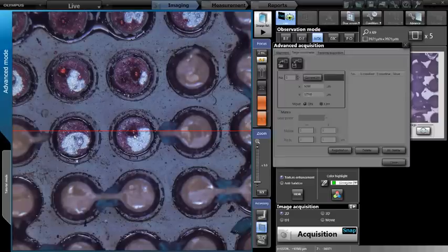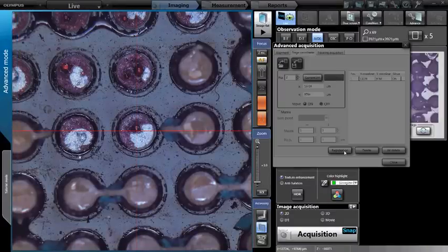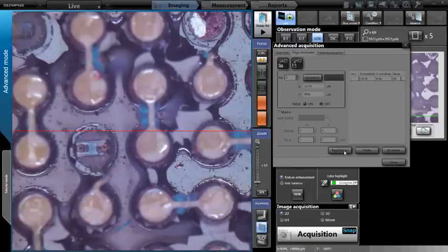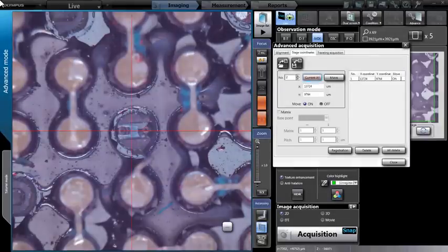Double-click to center on the first inspection point. We will now select Current XY to read the values of the first point. We then select Registration at the bottom to create our first point in the list. We will now move the stage using the joystick to the second point of interest on the sample. Once again, we will read the current XY position. We will select Registration to add the second point.